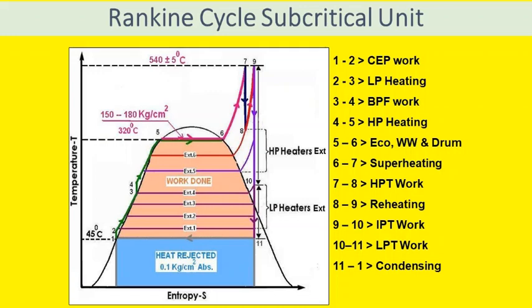And in the condenser we have circulating water continuously flowing through it, where heat is taken away from the exhaust steam to make it again into water or condensate, and that condensate is again pumped back to the boiler successively by CEP and BFP.